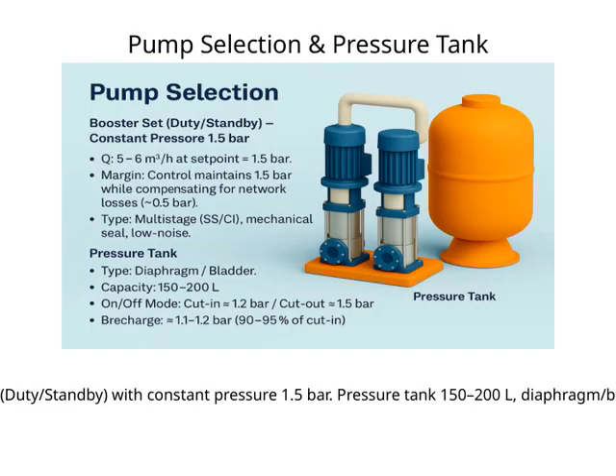Let's talk about pump selection and pressure tanks. When choosing a booster set, it's common to have a duty and standby pump configuration. This setup ensures reliability and continuous operation, especially during maintenance or if one pump needs servicing. We aim for a constant pressure of around 1.5 bar, which helps maintain consistent water flow throughout the system. Now, regarding the pressure tank, a capacity of 150 to 200 liters is typically suitable for many applications. The type of tank used is usually a diaphragm or bladder tank, which effectively isolates the water from the air cushion. This design helps maintain steady pressure and reduces pump cycling, ultimately extending the lifespan of your equipment. Connecting these points, selecting the right pump and tank ensures your system operates smoothly, efficiently, and reliably, aligning with the overall goal of a well-designed water supply system.